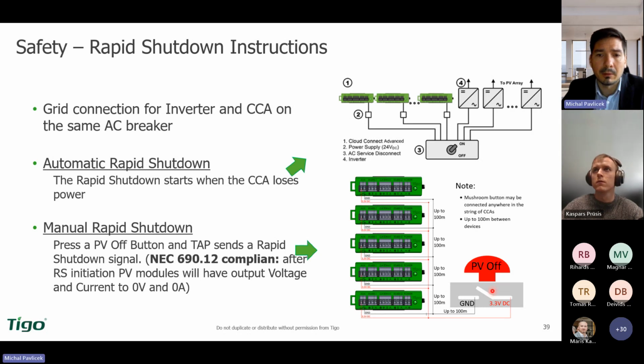That is a great feature for service. So for instance, you want to go on the roof, you would like to check the cables, maybe you would like to do some cleaning of the PV module. So what do you do? You click this button, just click, and it automatically switches off. So you can go on the roof, you can even touch cables, you can put a finger inside if you prefer, but I still don't recommend it. Because the voltage is below 24 volts, so you can even touch it. And such a case is excellent because you can just disconnect and connect the power plant in a very easy mode.